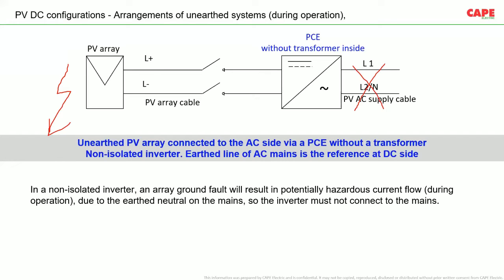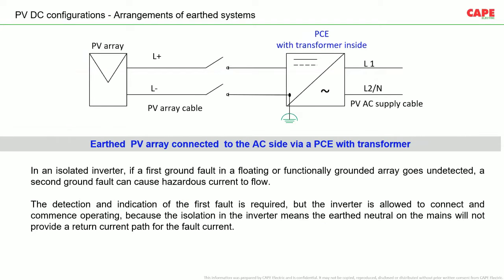Now, in a non-isolated inverter, an array ground fault will result in potentially hazardous current flow during operation due to the earth neutral of the mains, so the inverter must not connect to the mains. Another condition, PV DC arrangement of earthing system.